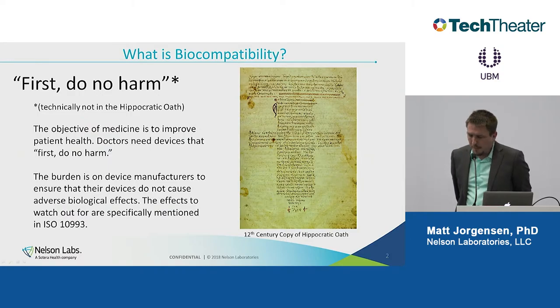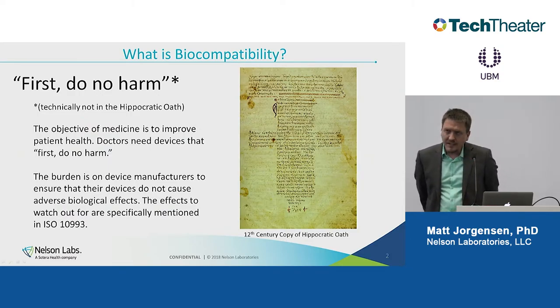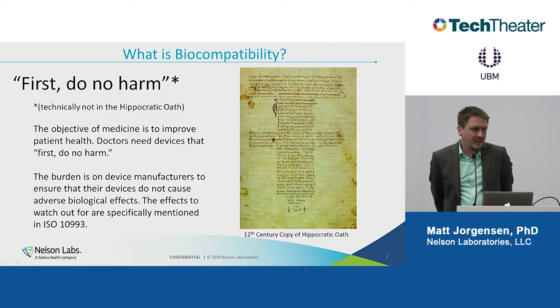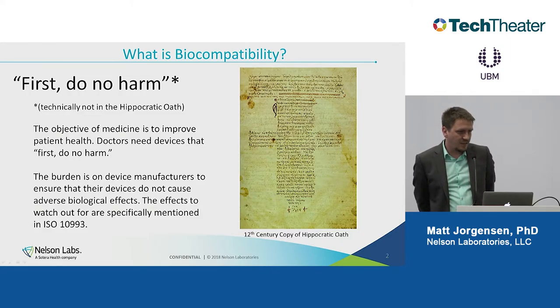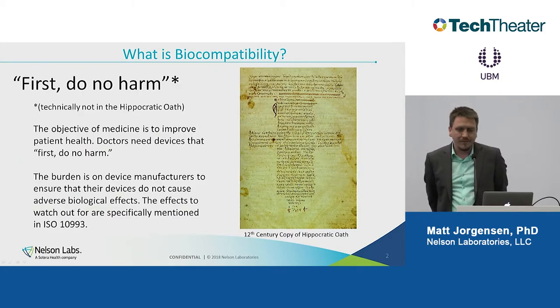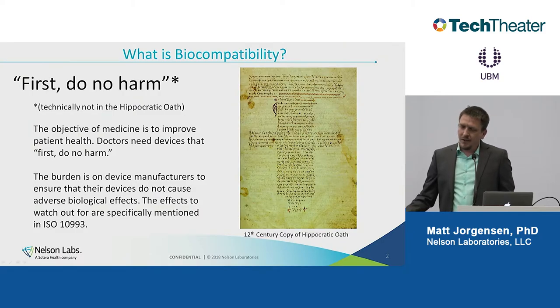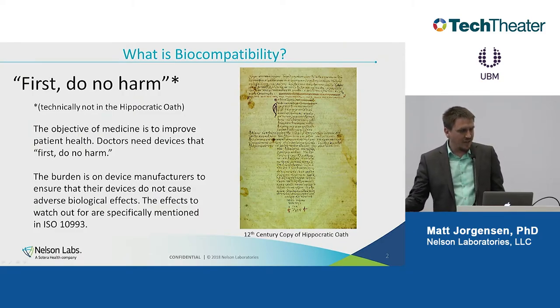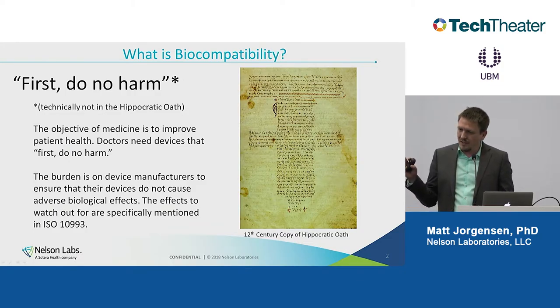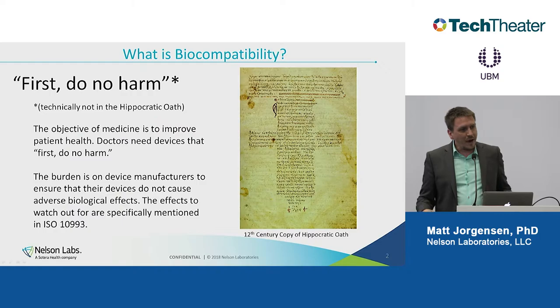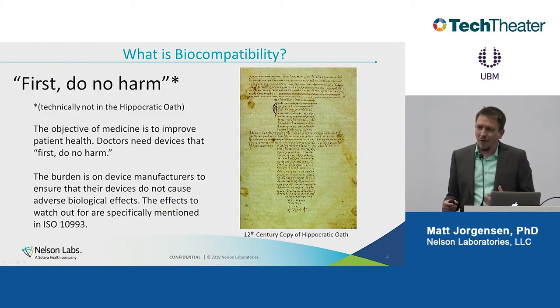But of course, biocompatibility is going through this process where you want to try to demonstrate that your device, first of all, is not going to harm a patient. So if you make and market a medical device and you start to think about all of the things that can go wrong, what we do with sterilization is make sure your device doesn't give somebody an infection and kill them before it can help them. It's the same with something like BET, we want to prevent the thing from giving you a critical fever. And biocomp is more like preventing the device from killing you slowly, over time, something like that.